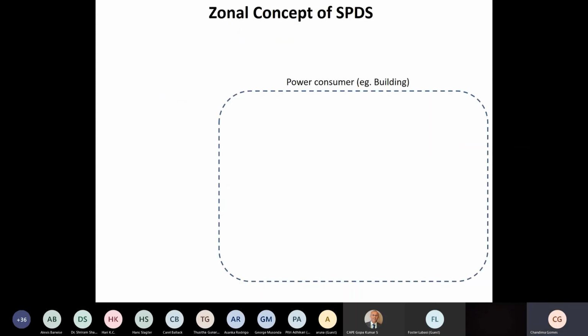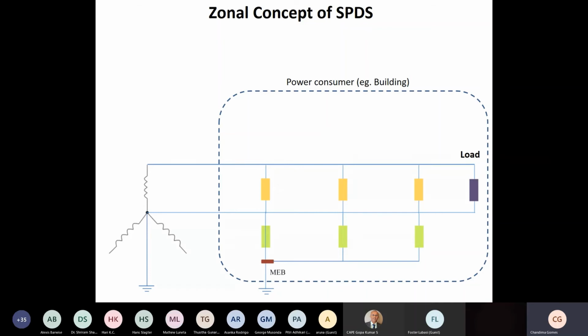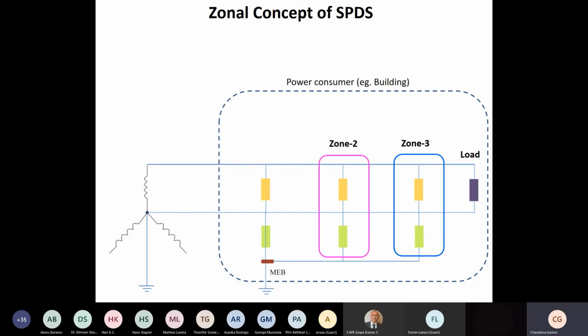Now, because of that, when you are selecting SPDs, we have to consider that first factor I told you, where to connect. So if there is a building, then you have to connect these SPDs at various places with varying specifications. Closest to the load, we call it zone 3, it may be zone 4, 5 and so on as well, but usually in most of the cases it is zone 3. These are the plug point level where you get the power to feed your equipment. Then zone 2, usually the sub panels. Then zone 1, which is the main panel where the wires are coming, the power supply is coming from outside.